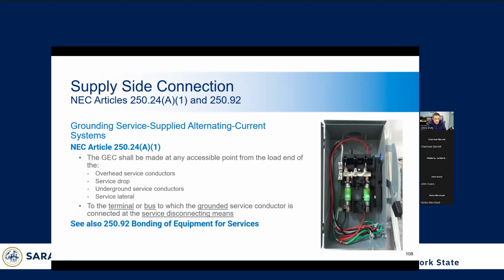Here we see a supply side disconnecting means that has a proper neutral to ground bond right here. You can clearly see the white neutral conductor entering from the top on the left side, and the green bonding screw effectively bonds the neutral to the enclosure, and that's done properly.